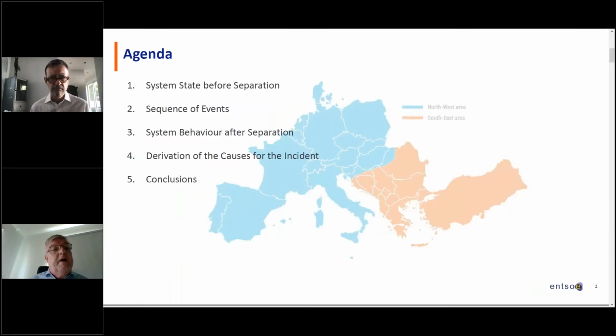I will show you the system state as it was before the separation of the grid. Already out of focus you can see behind where the split was, the Balkan area plus Turkey, which was split apart from the rest of continental Europe. There's the sequence of events, then what happened after the separation. We'll look at the causes of the incident, related conclusions, and from the causes we can already say what recommendations there are to mitigate them.